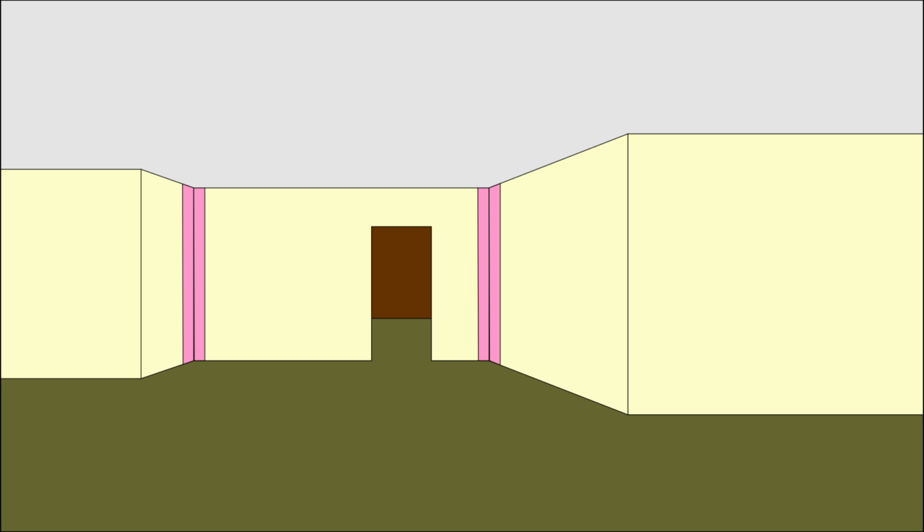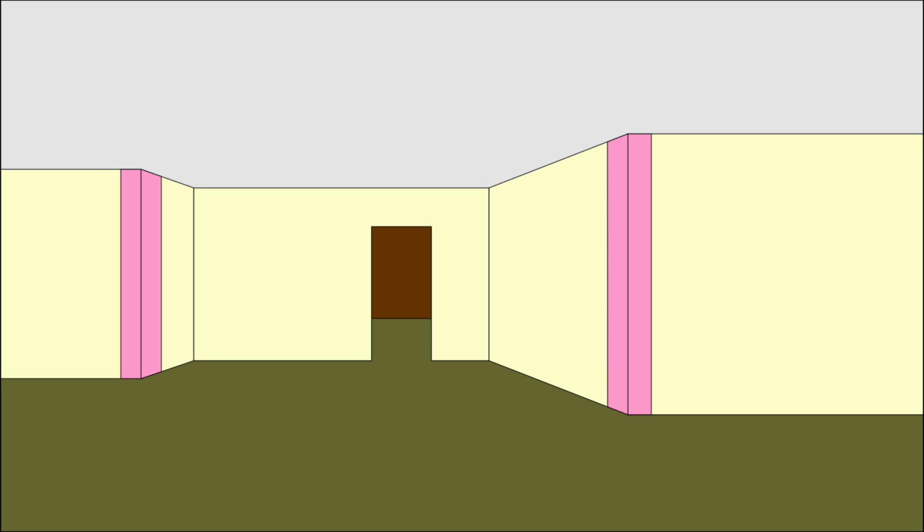Now, another thing which may not be immediately obvious here, and a lot of diagrams actually don't bother to put in, is it's not just the corners as we've got shown here, which you might sort of class as internal corners. You can also have the external corners as well, and again we've shown these here highlighted in pink. So it's not just the internal corners, of course a lot of rooms only have internal ones, it is the external corners as well, and again it's the same as before, the 150mm from the corner, and again that's a pretty wide zone there to install your cables in.